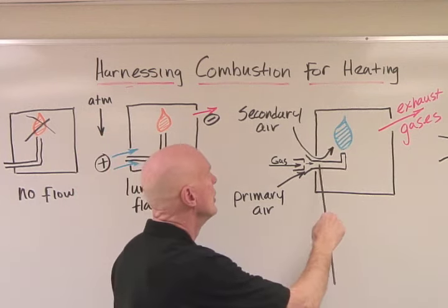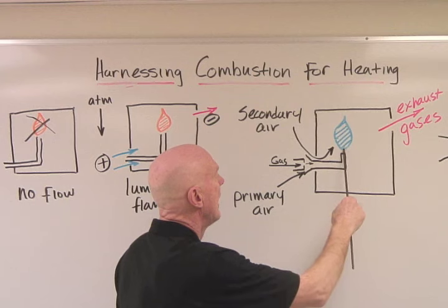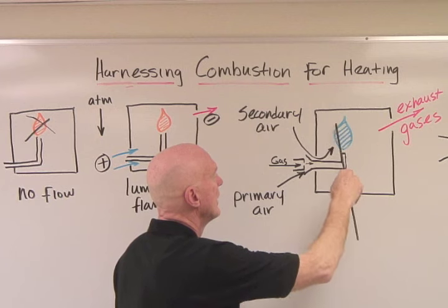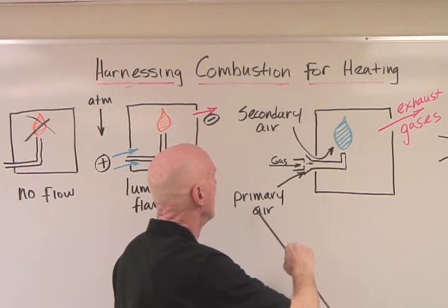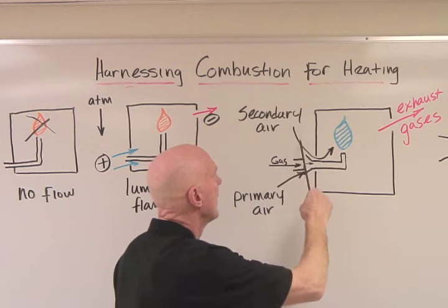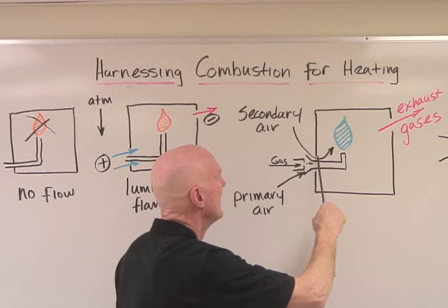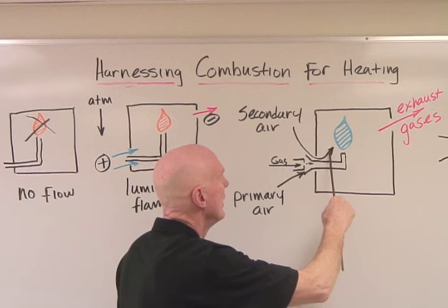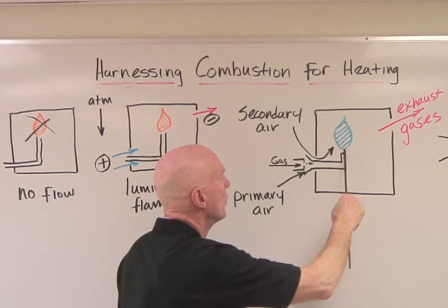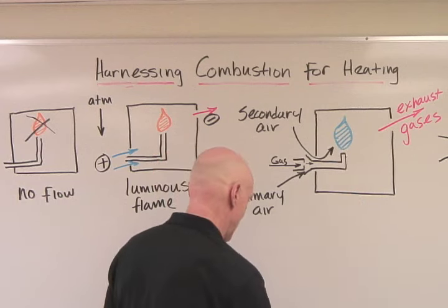And so you end up getting a more sophisticated flame. It's a blue flame. Got primary air coming in, being mixed in the burner. Then we have secondary air that's coming in just through a hole here in the burner.